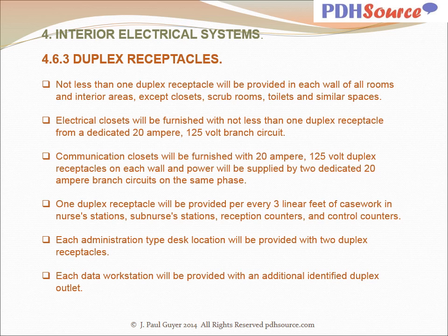Electrical closets will be furnished with not less than one duplex receptacle from a dedicated 20 amp 125 volt branch circuit. Communication closets will be furnished with 20 amp 125 volt duplex receptacles on each wall, and power will be supplied by two dedicated 20 amp branch circuits on the same phase. One duplex receptacle will be provided per every 3 linear feet of casework in nurses' stations, sub-nurses' stations, reception counters, and control counters. Each administration-type desk location will be provided with two duplex receptacles. Each data workstation will be provided with an additional identified duplex outlet.